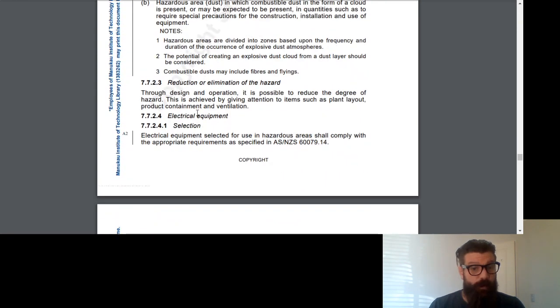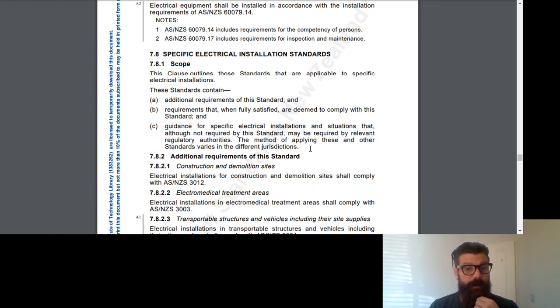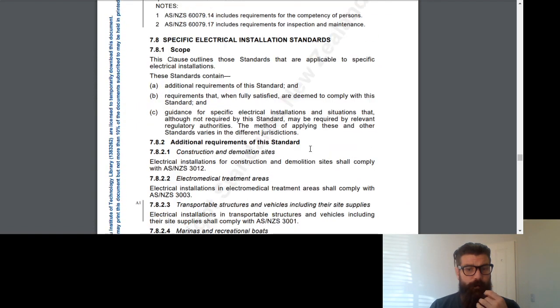If we look here at electrical equipment, so selection of electrical equipment, this is going to tell us the rules around what sort of equipment we can use within a hazardous area. And what does it say? Electrical equipment selected for use in hazardous areas shall comply with the appropriate requirements as specified in ASNZS 60079.14. So even though within this standard, ASNZS 3000, section 7 gives us rules around specific special installations, as we just said, it's actually going to refer us in the first instance to another standard, ASNZS 60079, which is the standard for hazardous areas. And you'll find if you go through section 7 and look at each of those different types of installation, it's going to refer to those.